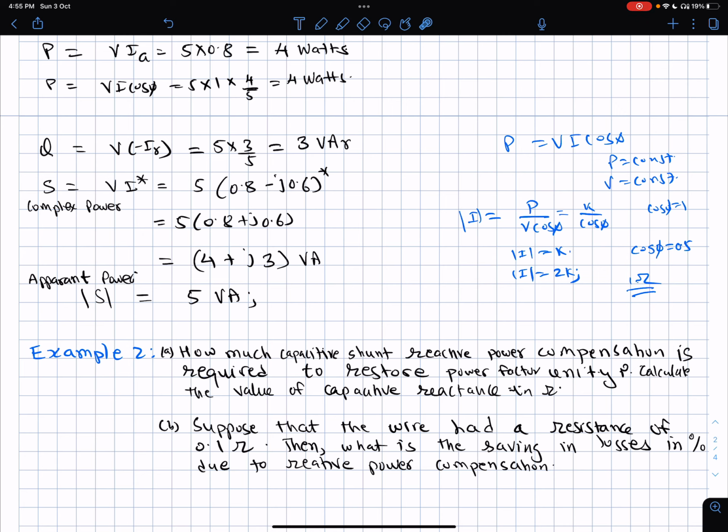So what we do is we connect, at our substation end, where we step down the power and pick it up from the utility, and where our metering is, just after the utility meter, a shunt capacitor to correct the power factor and restore it back to unity. So that power factor is also recorded in the meter. Looking at our power factors, they won't penalize us for bad power factor.